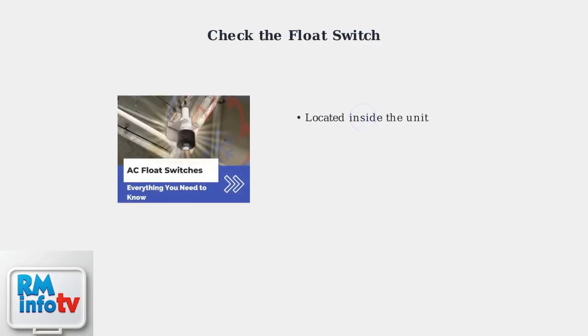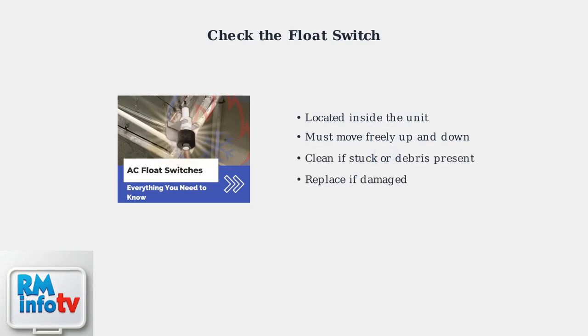The first component to check is the float switch. This small device detects water levels in the collection tank. If it gets stuck or malfunctions, it can trigger the E5 error even when the tank isn't actually full.